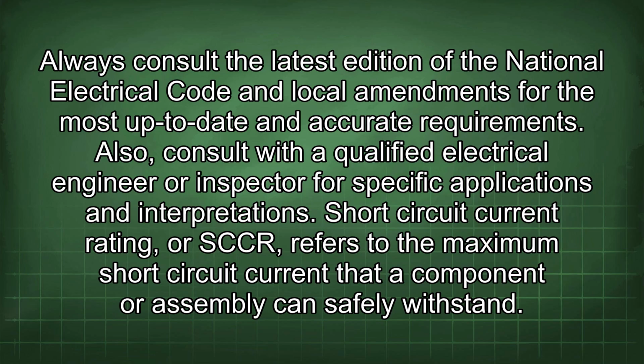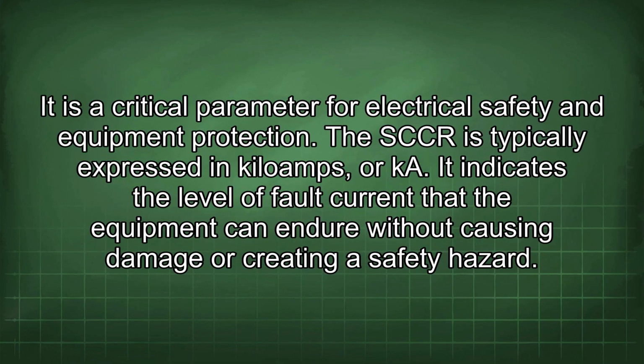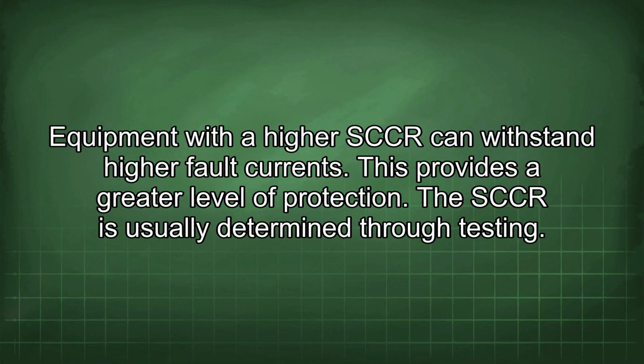Short-circuit current rating, or SCCR, refers to the maximum short-circuit current that a component or assembly can safely withstand. It is a critical parameter for electrical safety and equipment protection. The SCCR is typically expressed in kiloamps, or kA. It indicates the level of fault current that the equipment can endure without causing damage or creating a safety hazard. Equipment with a higher SCCR can withstand higher fault currents. This provides a greater level of protection.